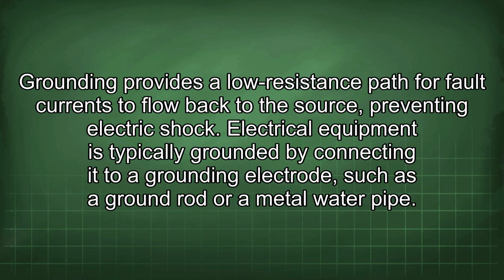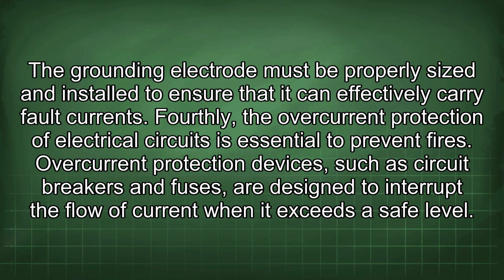Thirdly, the grounding of electrical equipment is crucial for safety. Grounding provides a low resistance path for fault currents to flow back to the source, preventing electric shock. Electrical equipment is typically grounded by connecting it to a grounding electrode, such as a ground rod or a metal water pipe. The grounding electrode must be properly sized and installed to ensure that it can effectively carry fault current.